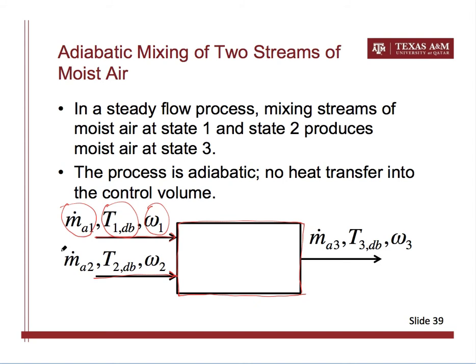Airstream one and airstream two each has a set of values for air flow rate, temperature, and humidity. After mixing, we have one mixed stream of air coming out of the control volume. This mixed airstream has a mass flow rate expressed in terms of dry air, and it must satisfy mass conservation. The mixed air will have a dry bulb temperature and a specific humidity that need to be determined based on the conditions of the two mixing streams — that's what the psychrometric chart analysis allows us to do.